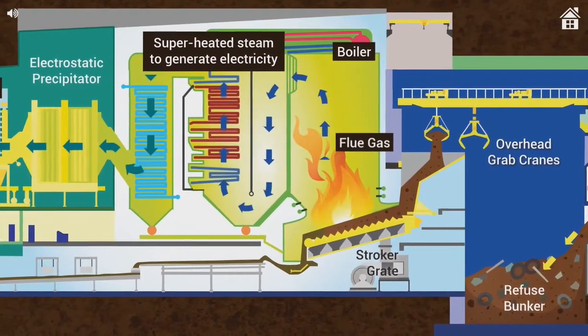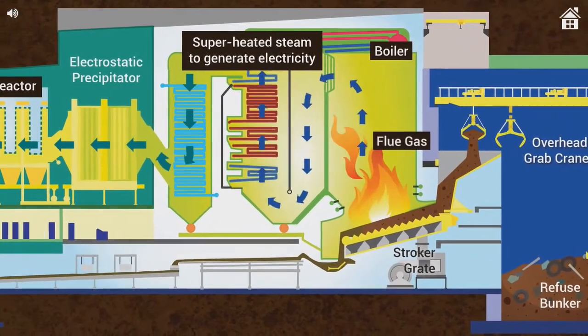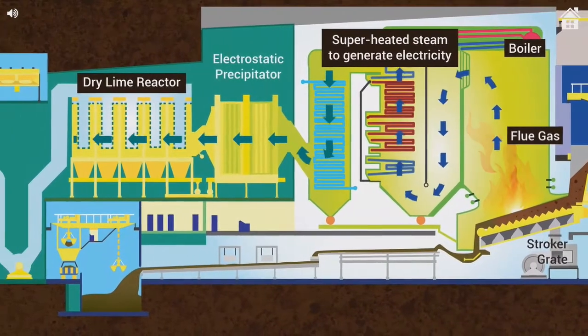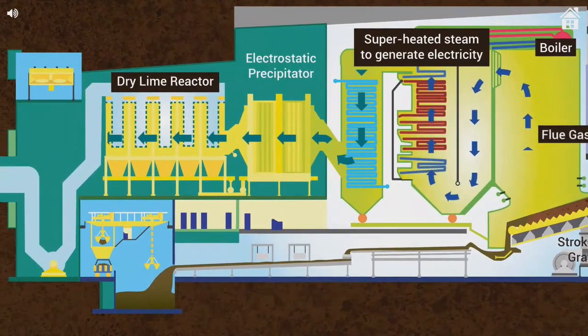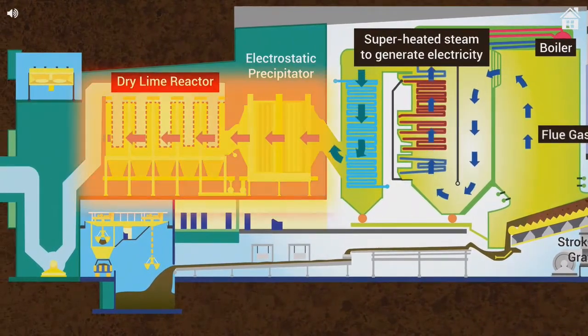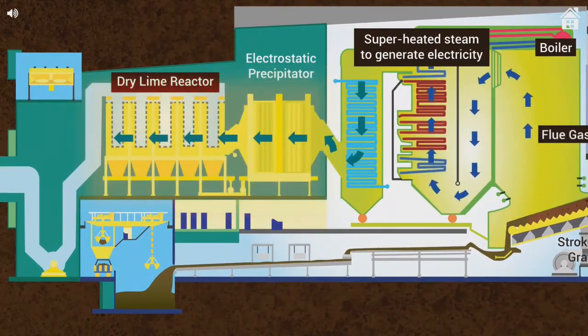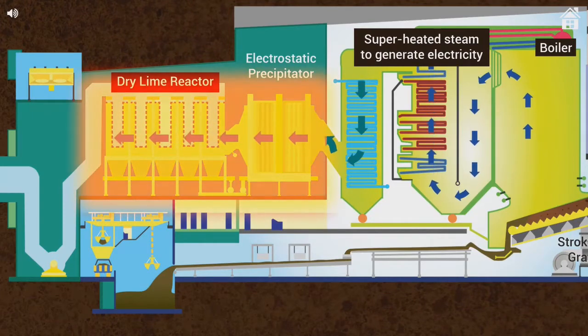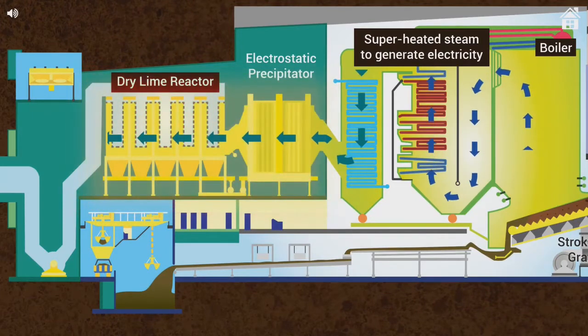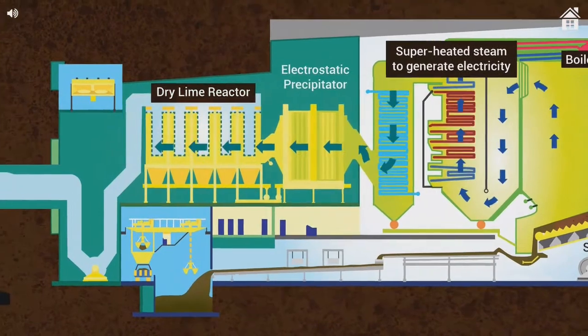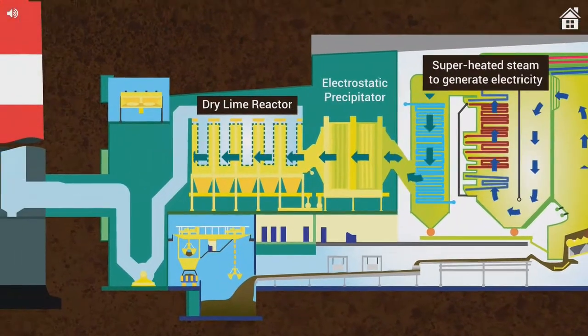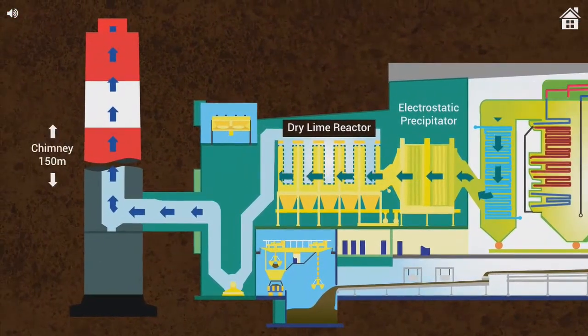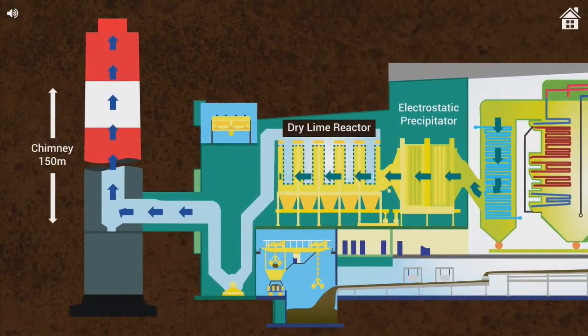The flue gas is cooled and then passes through a dry lime reactor and an electrostatic precipitator which will remove up to 85% HCl and 99.5% of the dust content in the flue gas. The flue gas is finally discharged to the atmosphere via chimneys that are 150 meters tall.